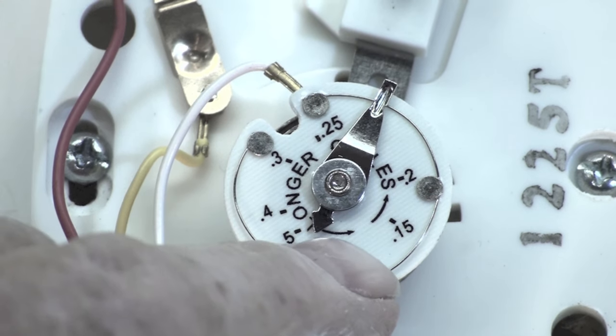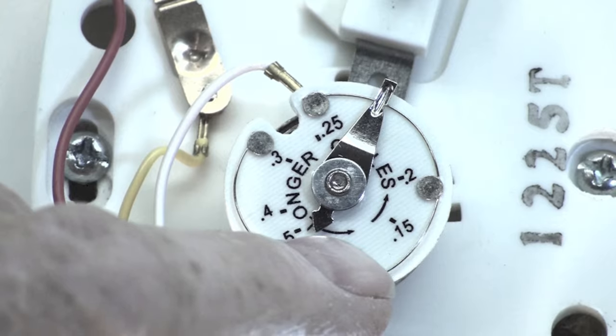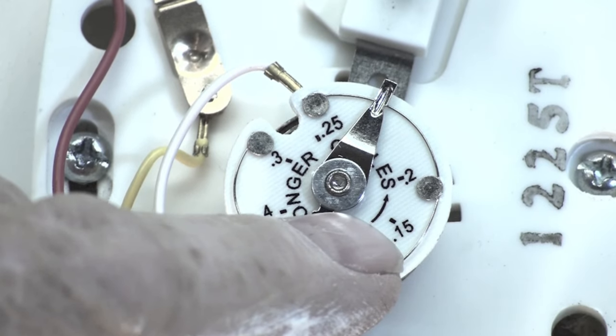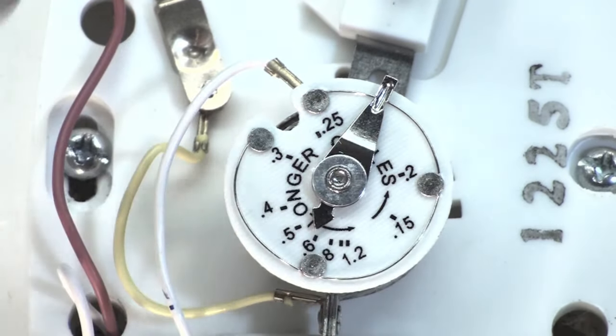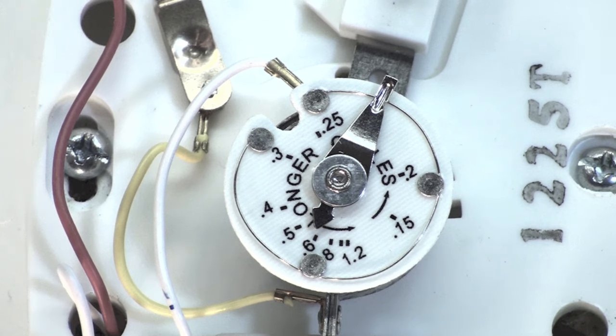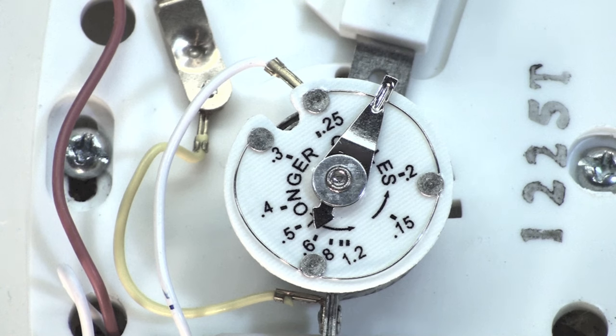So I'm limiting the length of the wire to match the amp draw of the circuit so I can get the same amount of heat out of the different lengths of the anticipator wire. Okay, this is a very simple and easy one to see.